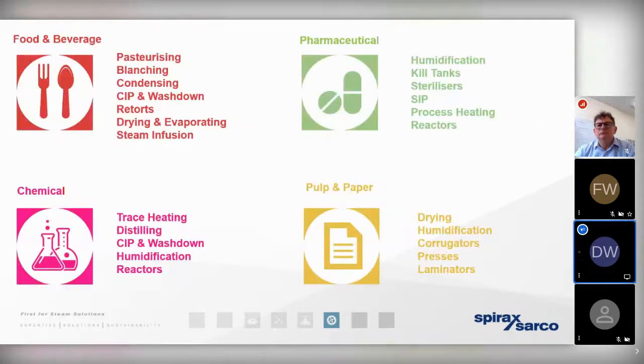But we all know that the vast majority of industrial applications are going to have a requirement for utilising thermal energy at temperatures far in excess of what low temperature hot water can provide. And this means that sources of low temperature hot water, that can be readily provided from ground source or air source heat pumps and are widely promoted in the building services sector, won't be enough. Whenever we're looking at industrial applications that need higher temperature sources of heat energy, then heat pumps simply aren't going to cut it. So simply put, there's always going to be an industrial requirement for steam in a significant number of process applications. We just need to be more innovative about how we generate, control, distribute, and ultimately use that steam.